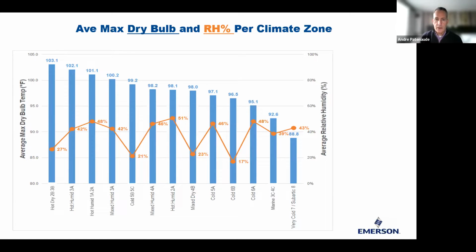And if you go to the next build, please, Derek, you'll notice that 4 of those climate zones are below 30%. And that's interesting because when you're drier, the impact of adiabatic gas cooling is much greater. Now above, when you build the next slide, you've got 9 out of 13 climate zones now where parallel compression is more energy advantageous annually than adiabatic. And maybe I'll show it again on the next slide.